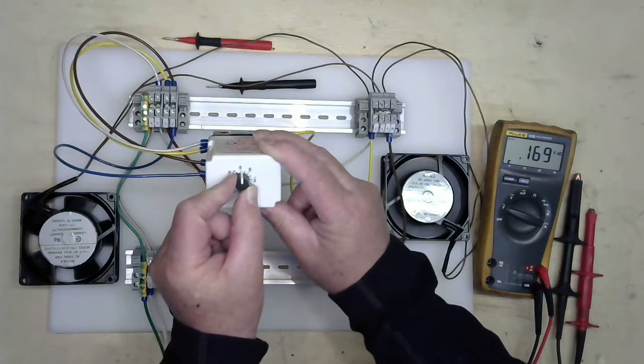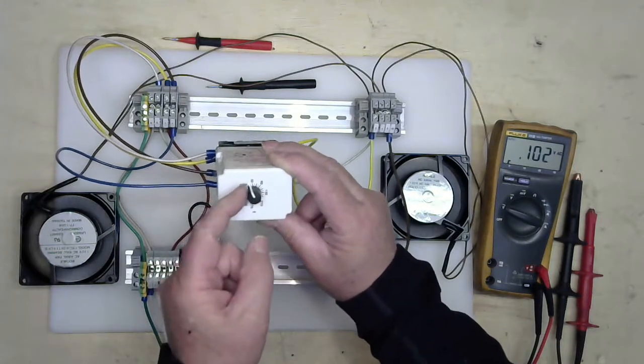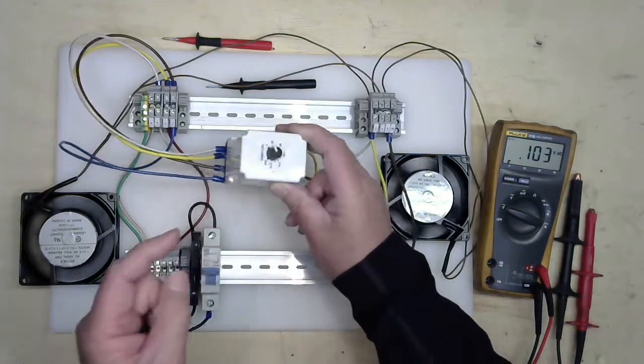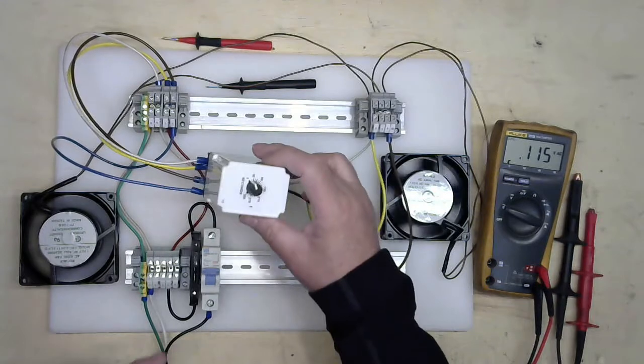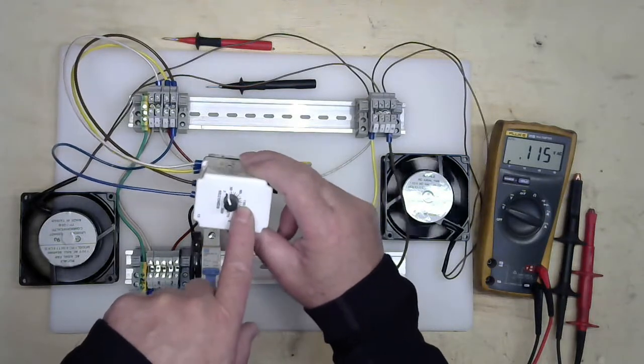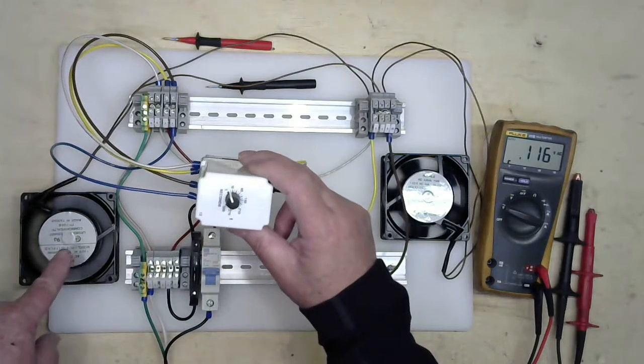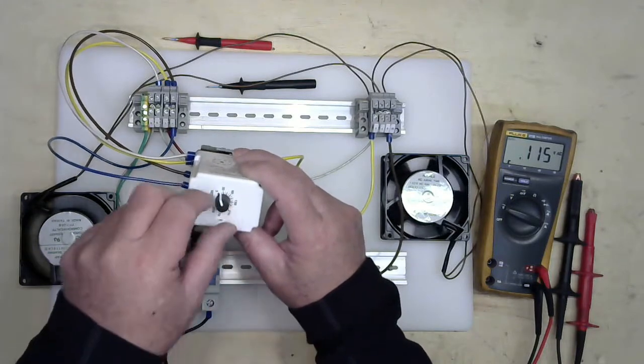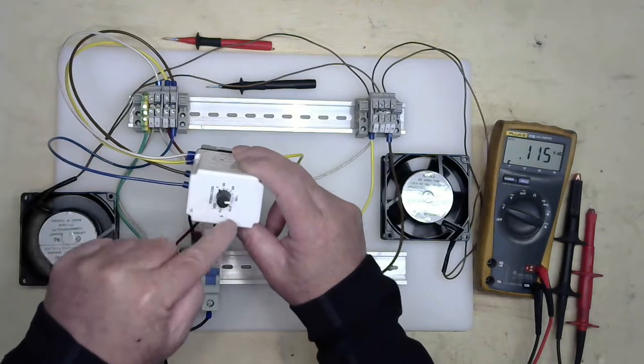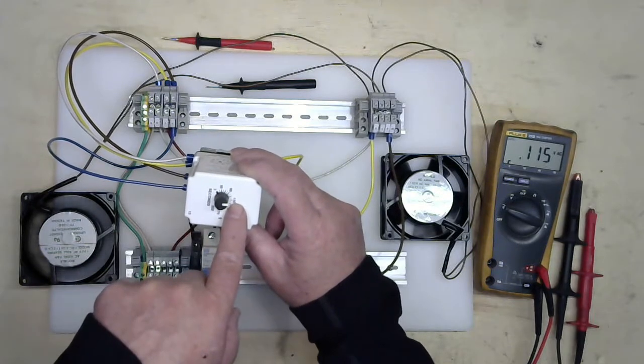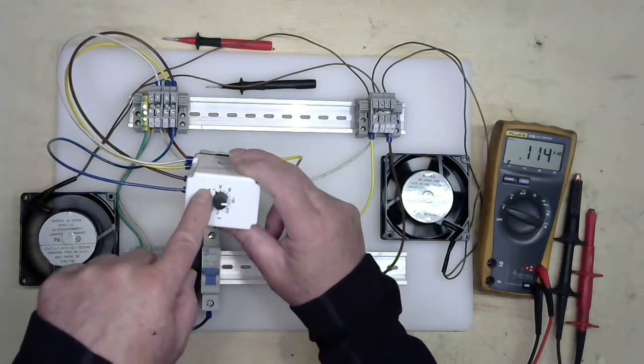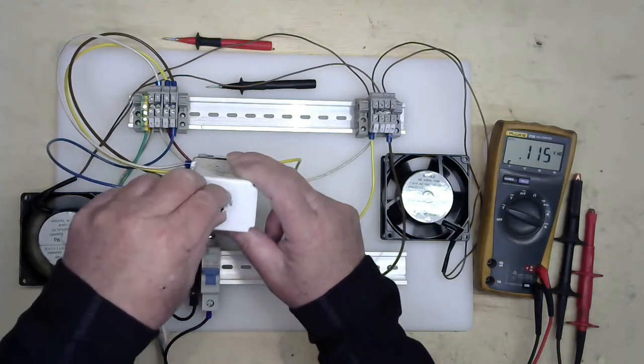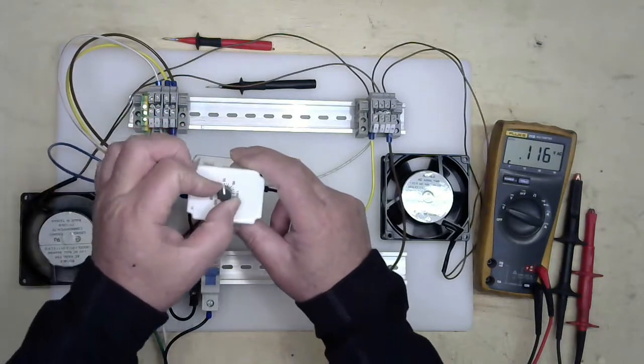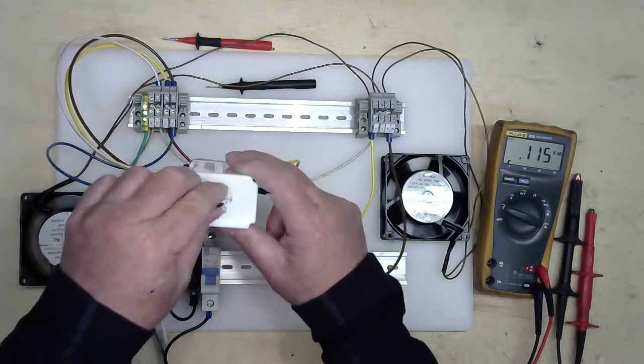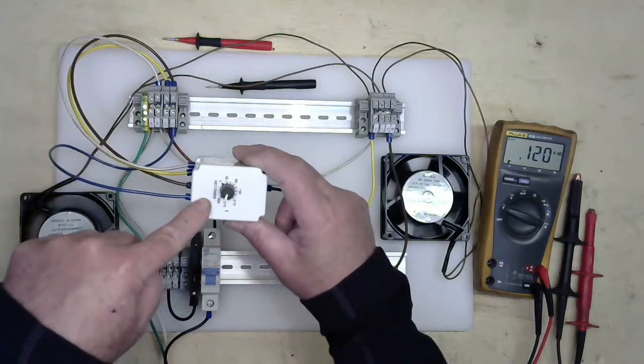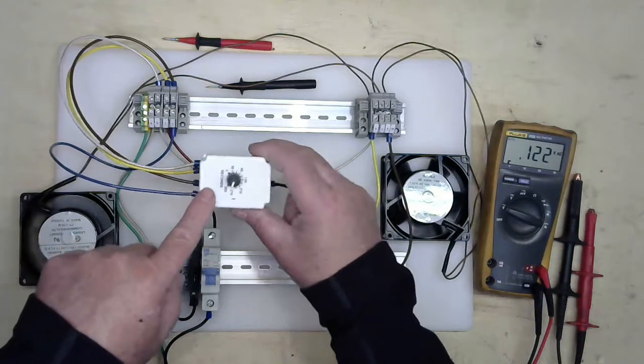you'll see, even though I already applied power, once my timer gets down to whatever time point I have set, it's automatically going to time out. So even though you set your timer at a higher time, if you want your second load to come on faster than your preset time, you can adjust the timing downwards. As long as we did not exceed the time that we had preset, the load will come on. If you want to increase or decrease it once the contacts have started, you have to de-energize the coil to your time delay in order for it to cycle again.